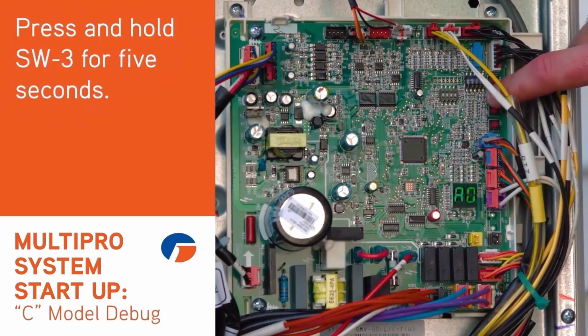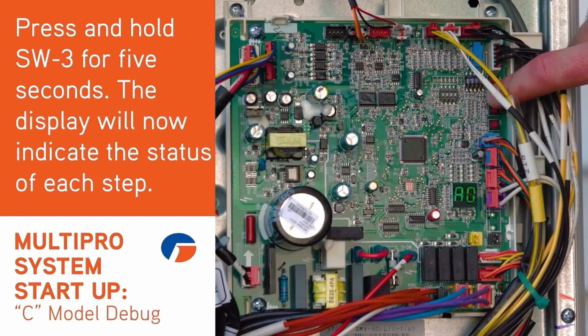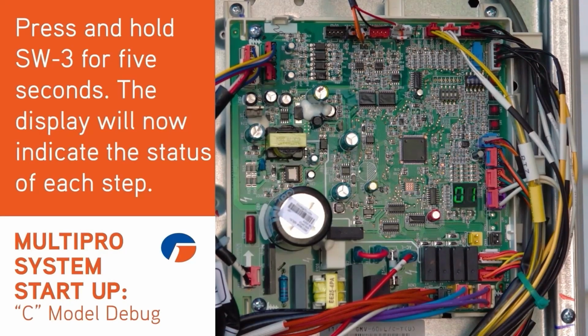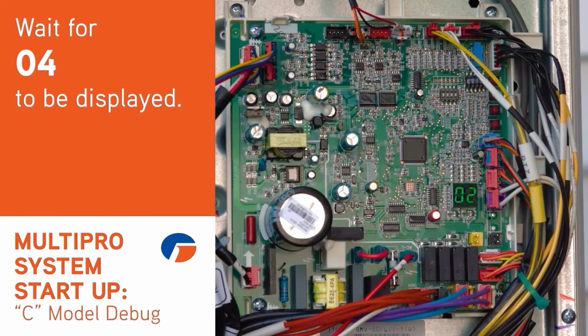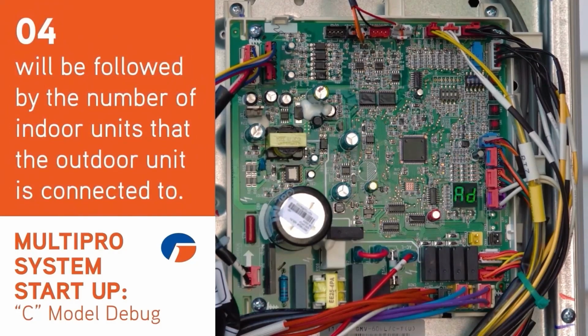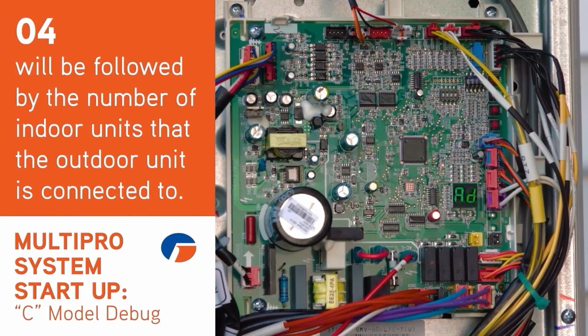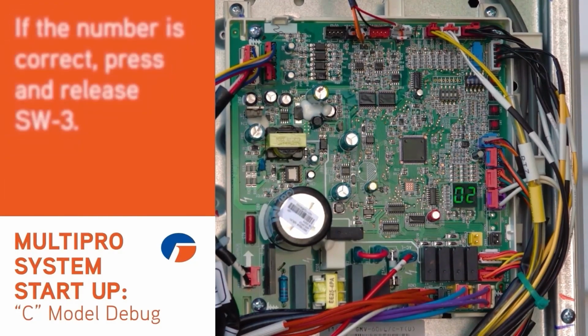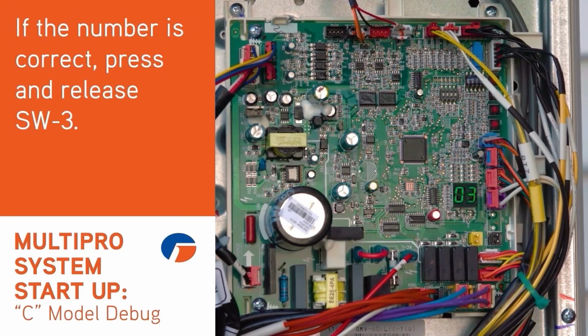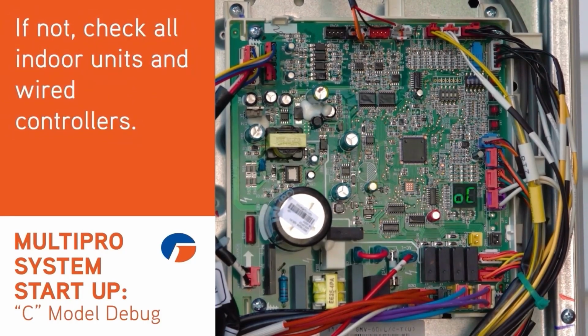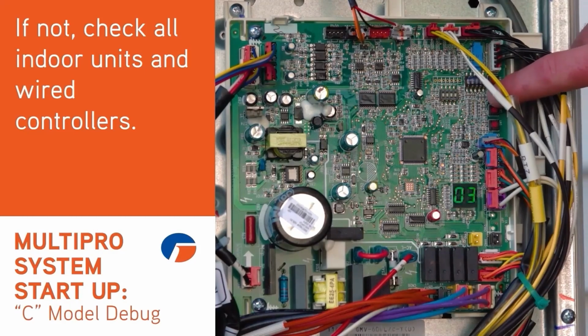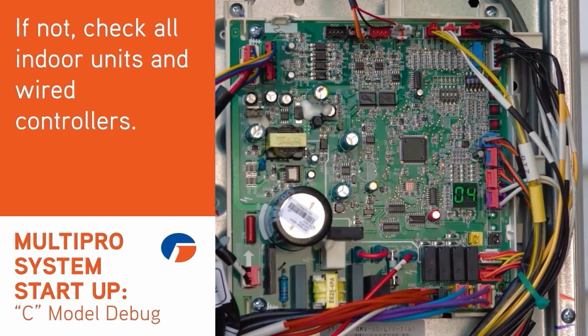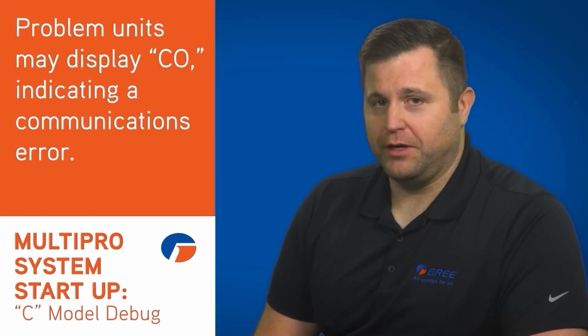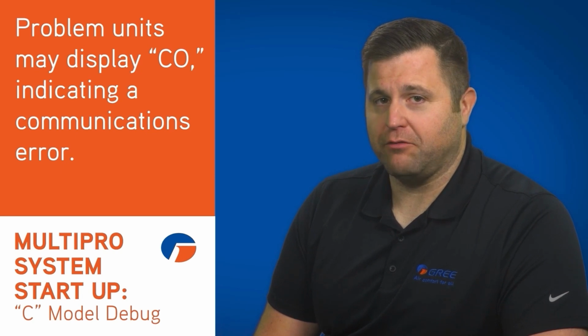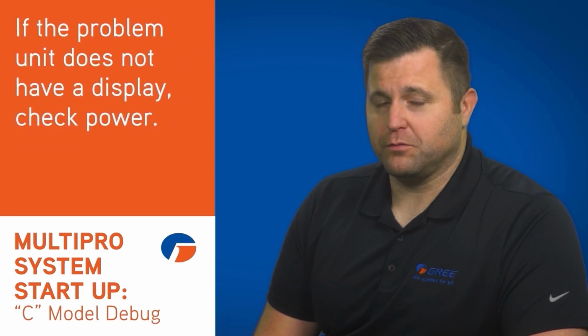Press and hold SW3 for 5 seconds. Once you let go, the display will change. This display will show the step and the status of each step. Do nothing until 04 is displayed. 04 will display, and then the number of indoor units the outdoor unit sees will be displayed. If this number matches, press and release SW3. If the number doesn't match, check all the displays on the indoor units or wired controllers to find out which one is not communicating. The problem unit will display C0, meaning a communication error, or the unit may not have a display. On the unit without displays, check power.